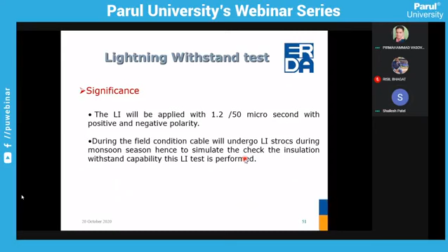High voltage test, this is the last test. After performing the lightning impulse test, 15 minutes later the high voltage test is carried out to check whether it has withstood the lightning impulse voltage test or not. And just for your information, for the type test, the high voltage test is carried out for 4 hours, at 4 times U0, where U0 is the phase voltage. Let us take the example of 11 kV: phase voltage is 6.35 kV, multiplied by 4, it is nearly about 26 kV, correct?